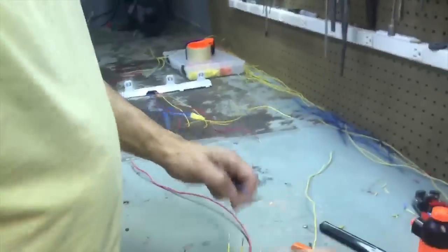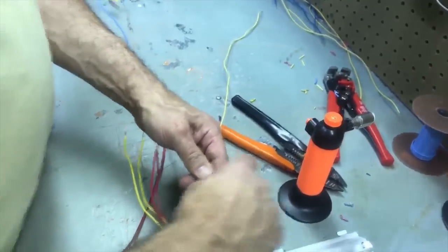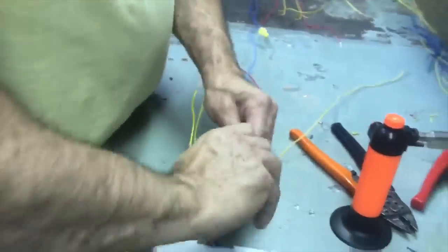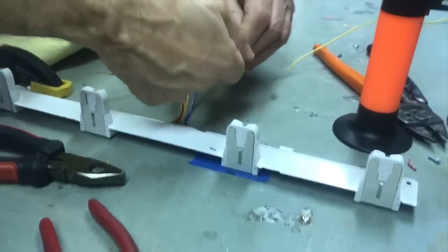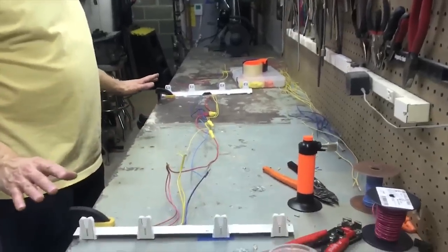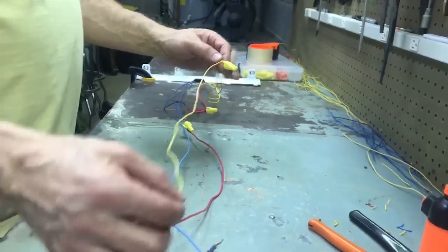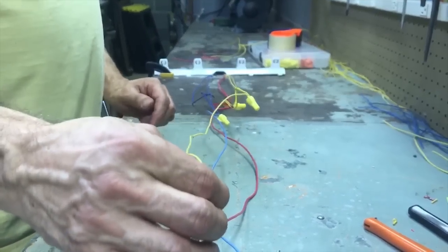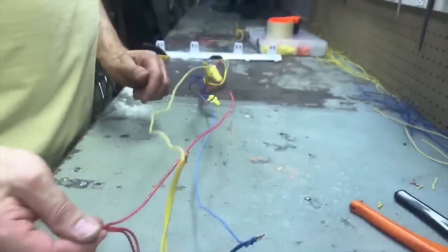On the back side you can do it either way — use a wire nut to put them together, or pliers. I find with the pliers it goes faster; once the wire starts twisting you back it off and it's ready to go into the ceiling. The wiring is all done and it's really simple: yellows are all hooked together, same with the reds, same with the blues. Then at the light fixture, yellow goes to white, blue goes to black — 'black and blue,' that's how I remember it — and red goes to red.